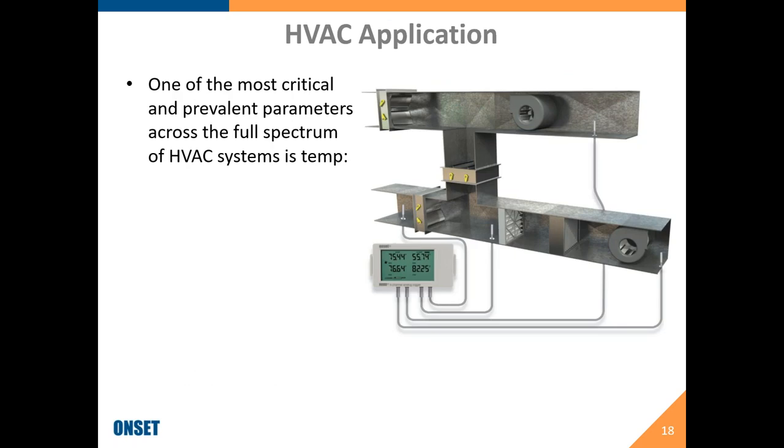The specific application that we'll talk about is trying to get a temperature profile out of a system. You'll see here that we have deployed one of the UX120-006M with a variety of temperature probes on it. They've been placed at several different points throughout the system so that the individual who's logging this can watch how the air flows and changes to see if there's any issues or obstructions in the system as a whole.